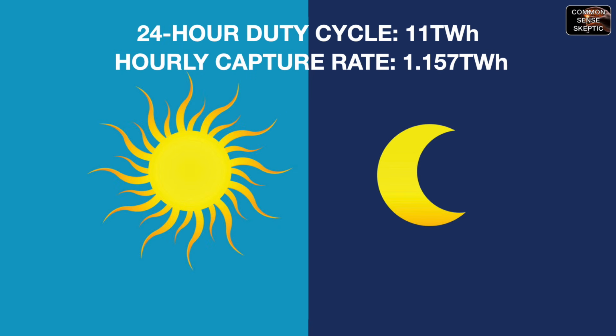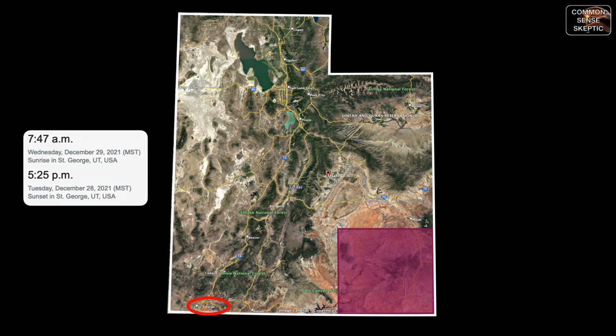Rounding up slightly, 11 terawatt hours need to be generated daily, with more than half of that being stored. In St. George, Utah, the shortest day of the year, the baseline as it were, has only 9.5 hours between sunrise and sunset. So the facility has only 9.5 hours to store the power needed to get through the remaining 14.5 hours of the day, or about 60% of the power needed over the course of the day, to accommodate nighttime requirements.